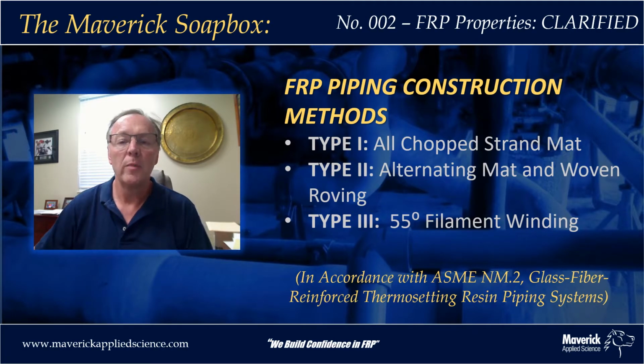So principally we're going to be talking about three construction methods for FRP. Type 1, all chop strand mat, type 2, alternating mat and woven. These two are considered hand layup pipe. And then type 3 is 55-degree filament wound pipe. Type 3 might be something new. This is a new designation in accordance with NM2, so that's what we're going to talk about today.